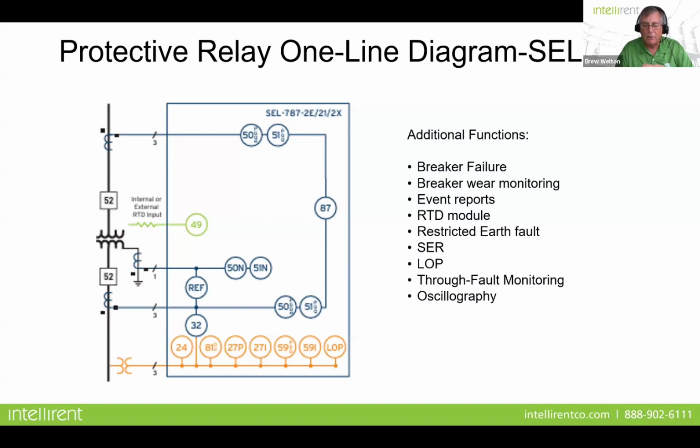And he goes out to the field, and by the time he gets there, the foreman of the substation group had the transformer completely disconnected, had scaffolding around, and was getting ready to do some thorough testing on the transformer. And so the technician walks up to him and says, well, by chance, did you look at the oscillography and the event record out of the relay? And being a substation maintenance guy, he was kind of dismissive. He said, "No, Sonny, go away. We got work to do. We got to figure out what's wrong with this transformer."